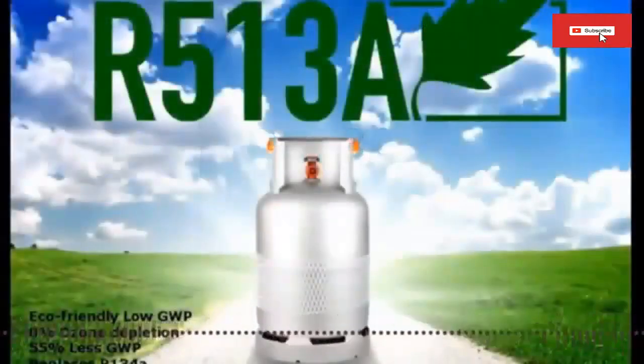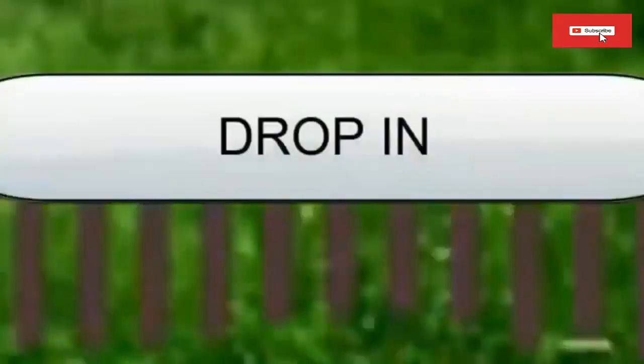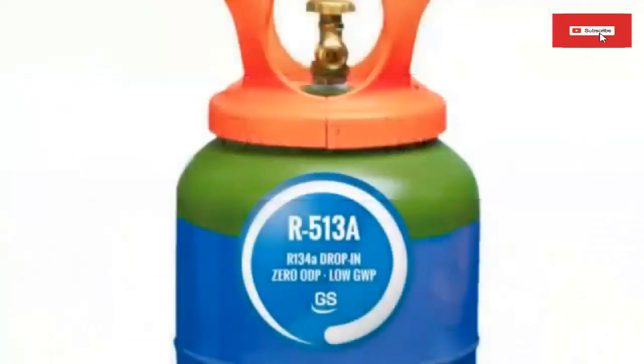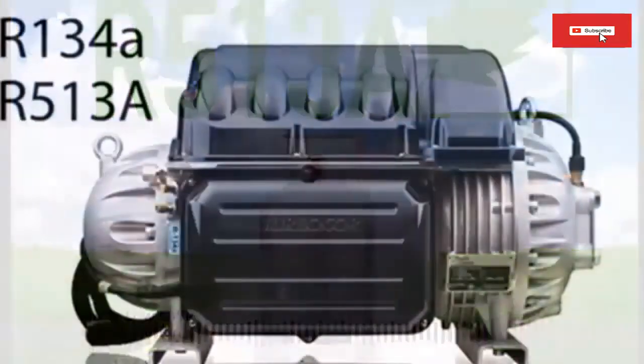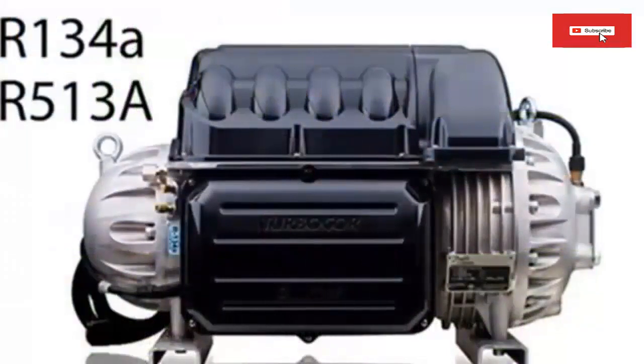4. R-513a refrigerant is a drop-in, direct replacement for R-134a in existing commercial and industrial refrigeration equipment of high and medium temperature, positive displacement and direct expansion. 5. In addition, R-513a refrigerant is presented as an excellent alternative in systems with centrifugal and screw compressors. 6. All Danfoss Turbocor series compressors, produced as of December 2017, are compatible with R-134a and R-513a.